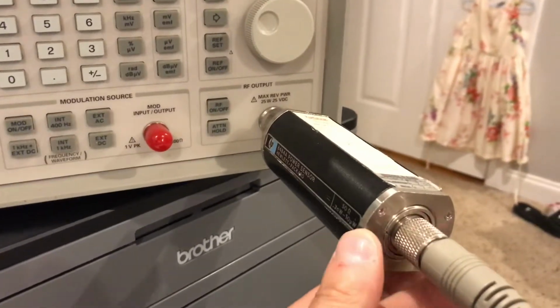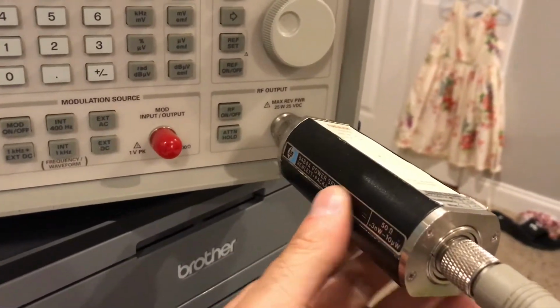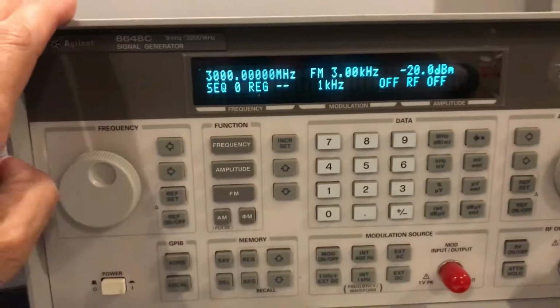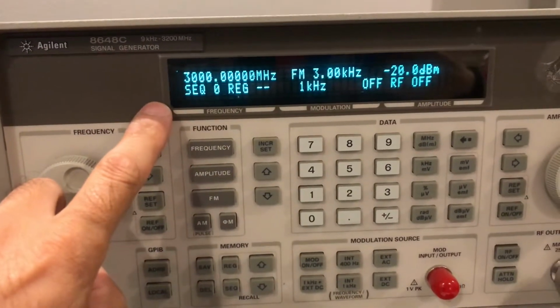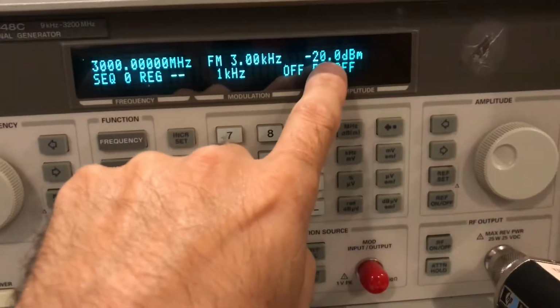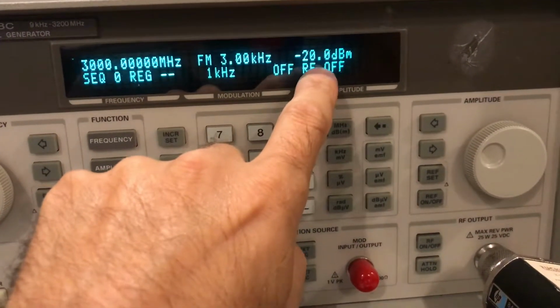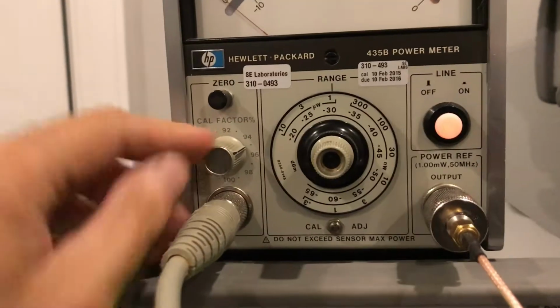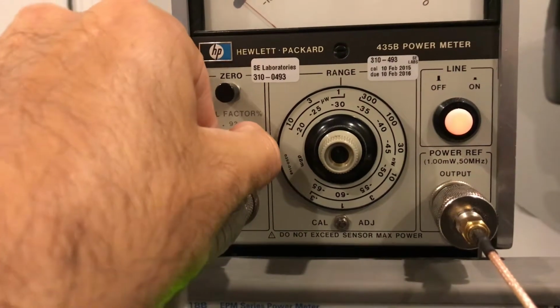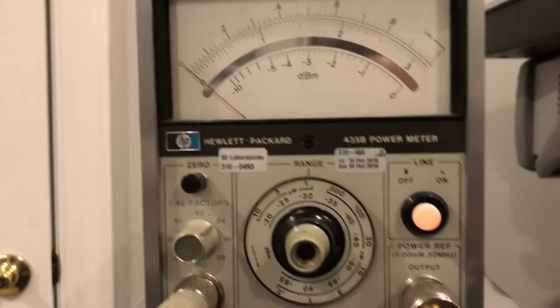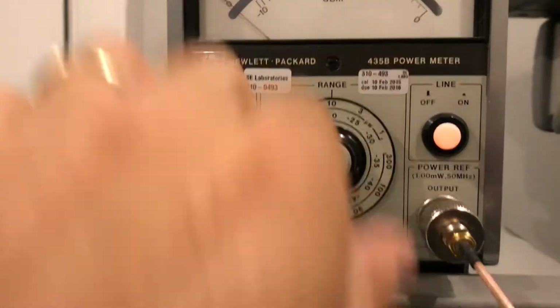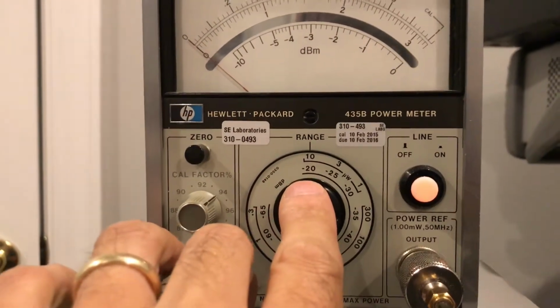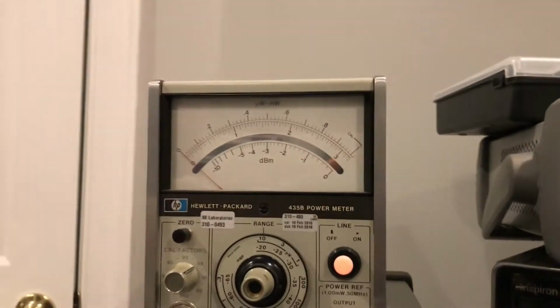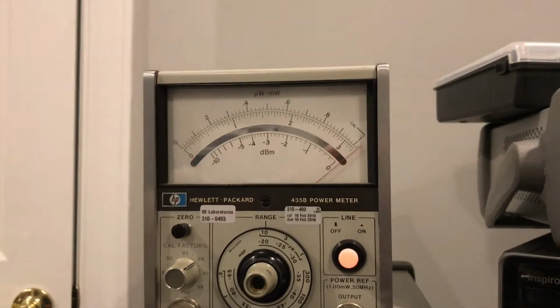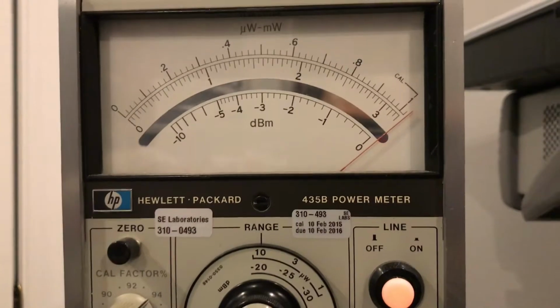Alright, so just to get rid of any losses in the cable, I've gone ahead and hooked the unit directly to the signal generator. We've got our signal generator set for 3000 megahertz, 3 gigahertz, with an RF output of minus 20 dBm. So I know based on the label on the sensor that we need to set our cal factor to 94, so we'll do that. And we'll go ahead and adjust our range to minus 20 dBm. And we'll put the RF on, and there is our RF.